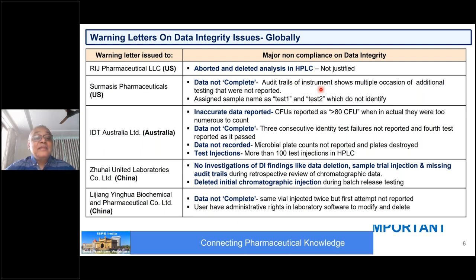So one company, for example, had aborted and deleted analysis in HPLC, which is not justified. It's not that you cannot abort or delete any run - you cannot delete obviously, but you can abort the analysis. If you want to abort the analysis, you should have a proper justification, whether it is because of power failure, some interruption, or malfunction of the HPLC, temporary malfunctioning, something like that. But you should have the justification for aborting the run into the HPLC.